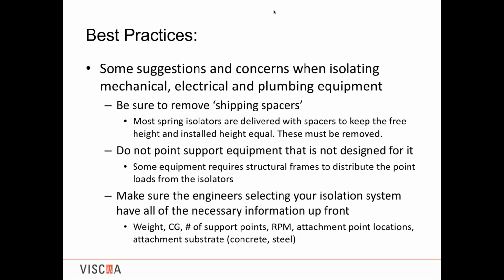And the next here is make sure the engineers selecting your isolation system have all of the necessary information up front. I read that because it's important. Without the weight of the equipment, the CG, the number of support points, RPMs, and such, we can't do our job and select the right isolation system. Once we start guessing or making assumptions, you know what happens. And so having all of that information up front, getting it from the manufacturer and everyone else is important to make the right selection.